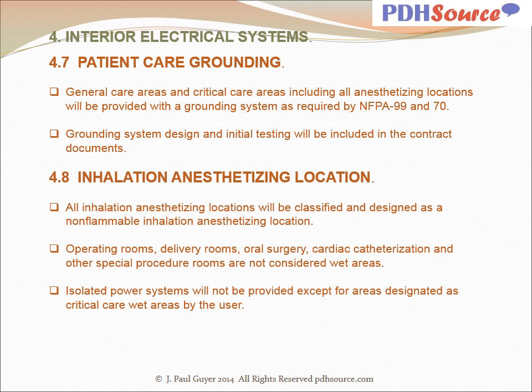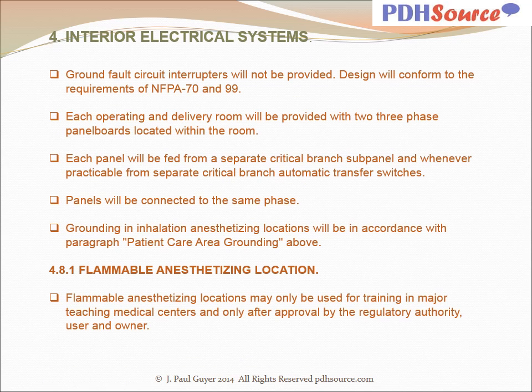Isolated power systems will not be provided except for areas designated as critical care wet areas by the user. Ground fault circuit interrupters will not be provided. Design will conform to the requirements of NFPA 70 and 99. Each operating and delivery room will be provided with 2 3-phase panel boards located within the room. Each panel will be fed from a separate critical branch subpanel, and whenever practicable, from separate critical branch automatic transfer switches. Panels will be connected to the same phase.